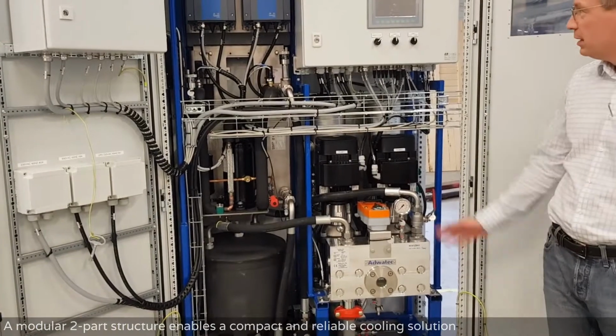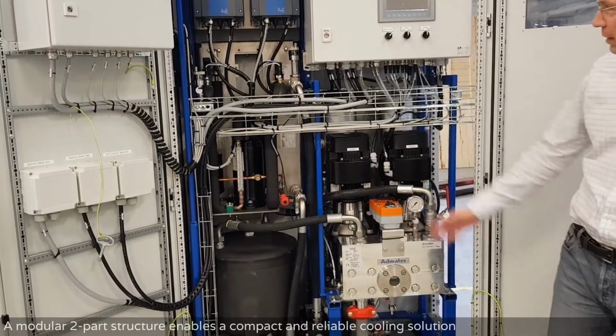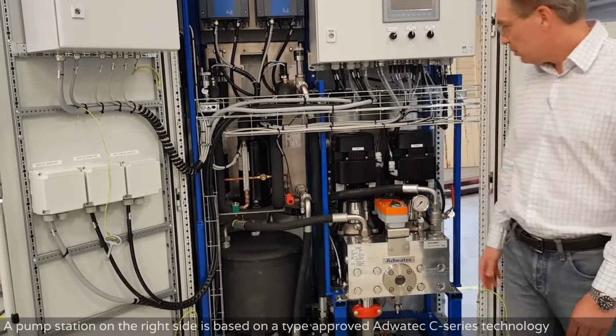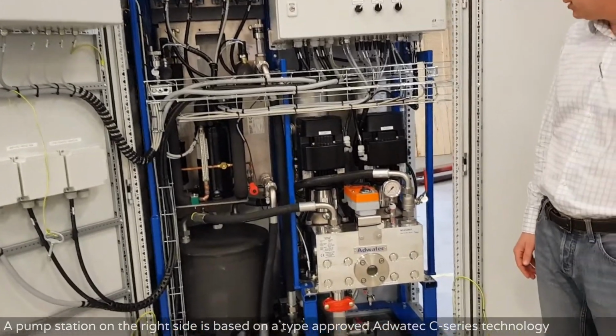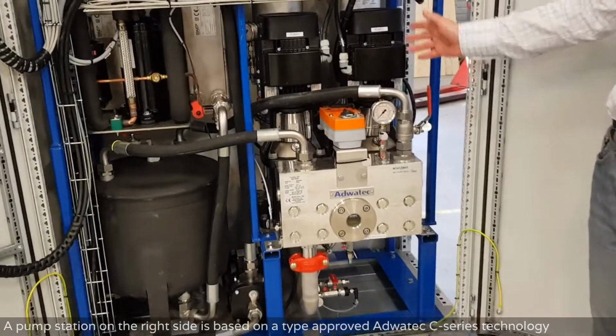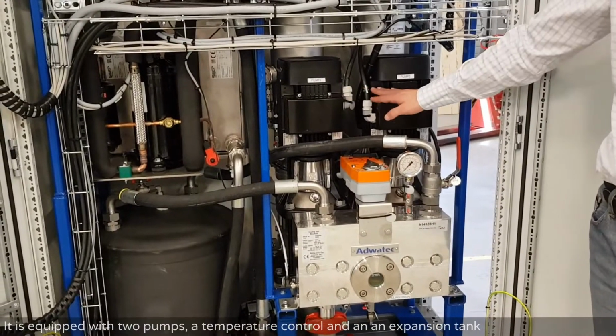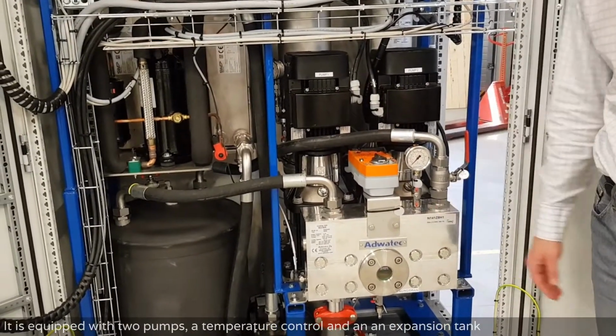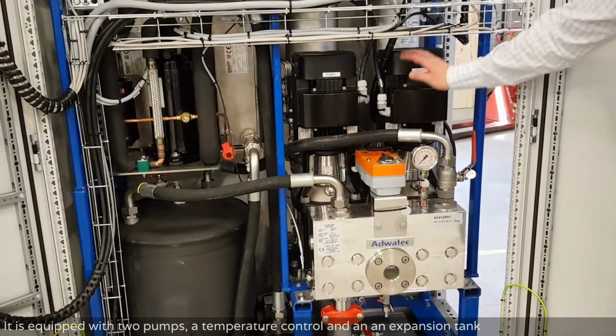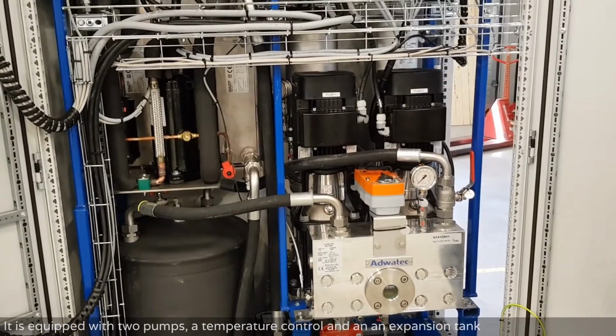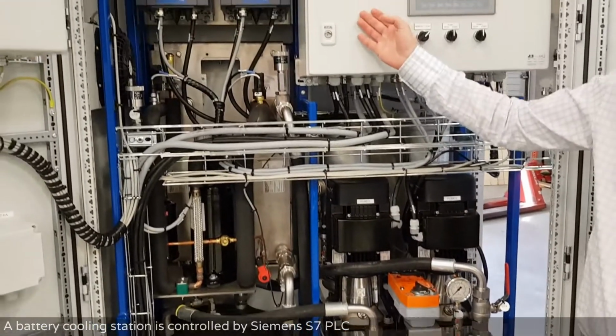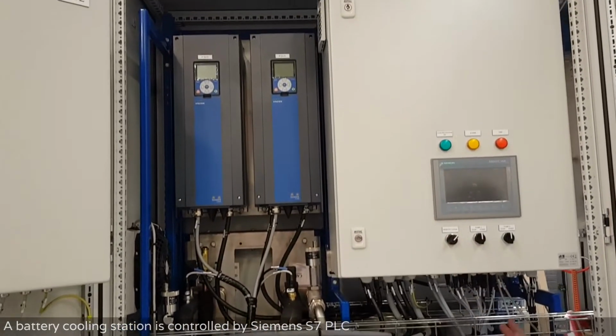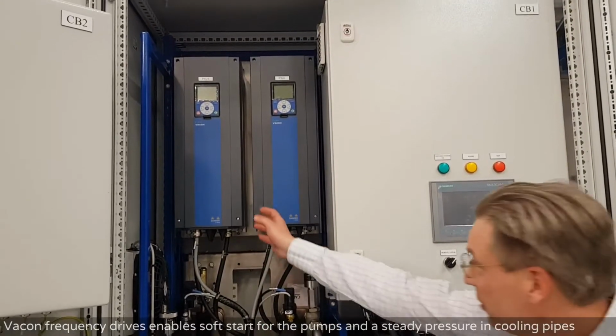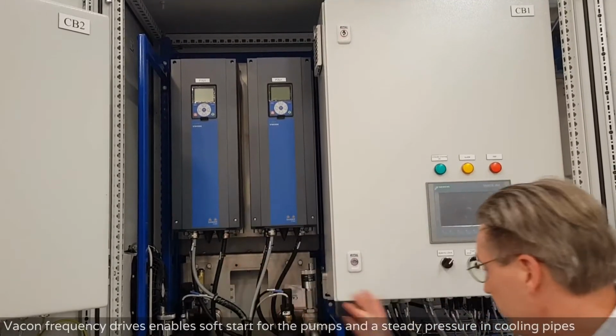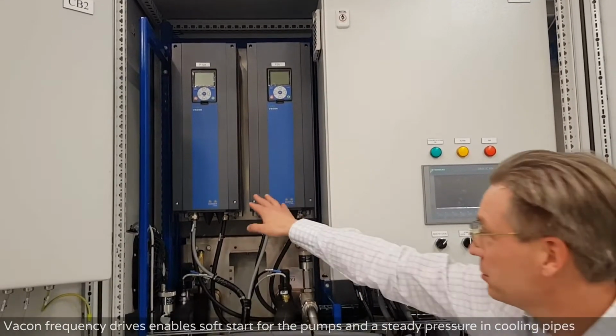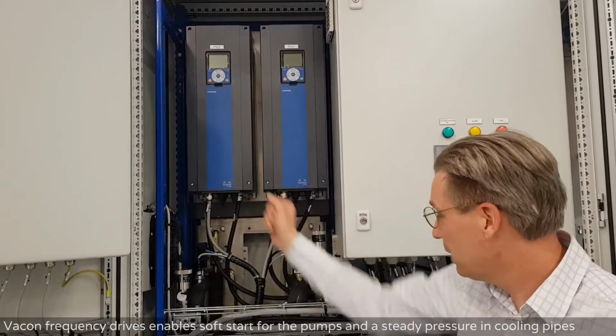It is made of a water cooling station part and a chiller part. The water cooling station is our normal water cooling station. In this case, we have a redundant system with two pumps, a manifold, a three-way valve, and water tanks here on the back. This cabinet is the control cabinet controlling the whole pump system. Up here we have the drives that control the pumps. The drives are quite big because this is a 690 volt version.